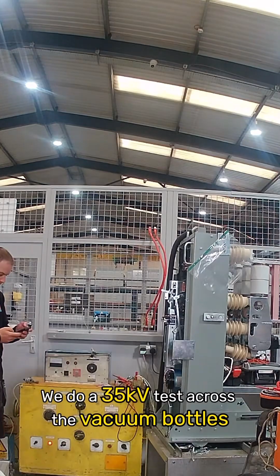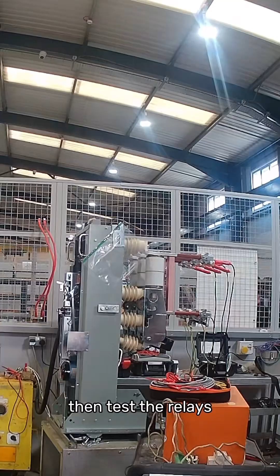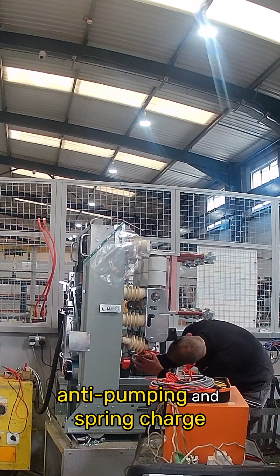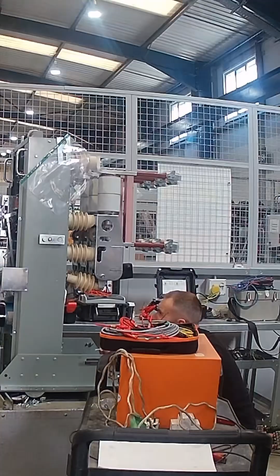We do a 35 kV test across the vacuum bottles, then test the relays, the motor contactor, anti-pumping and spring charge, plus all coil resistances.